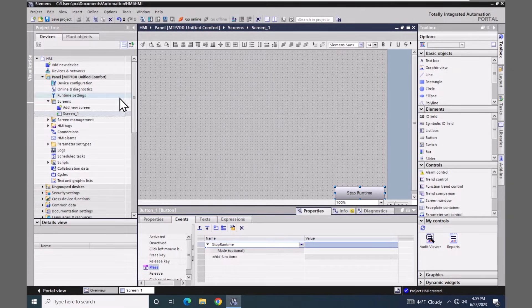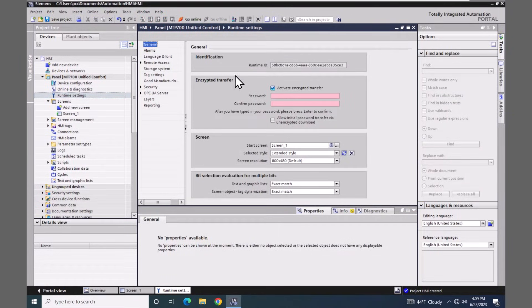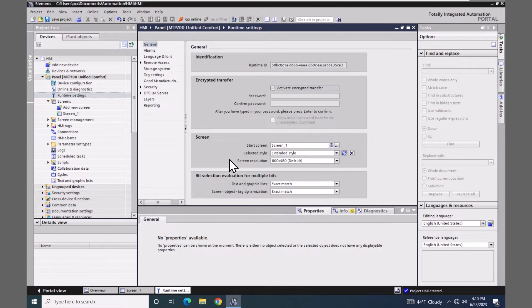The next thing I'd like to do when I add a new HMI to the project is go to the runtime settings. When I open up the runtime settings, the first thing I typically do is uncheck 'Activate encrypted transfer'. With this box checked I would have to enter a password each time I download to the HMI, so for demonstration purposes I am going to deactivate that option. In the screen area below you will see the screen resolution, which defaults to the resolution of the HMI device selected. I'm going to use the default screen at this point.